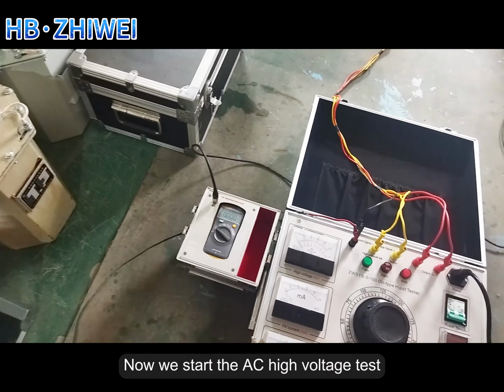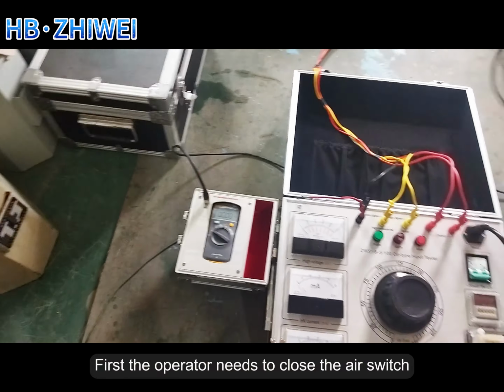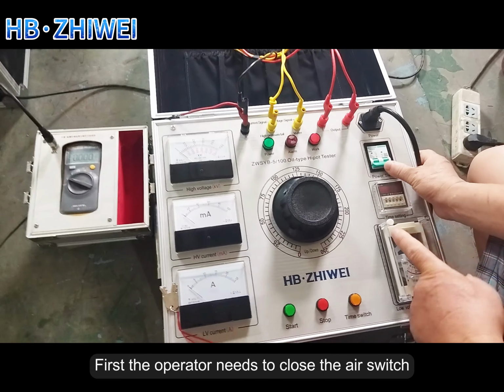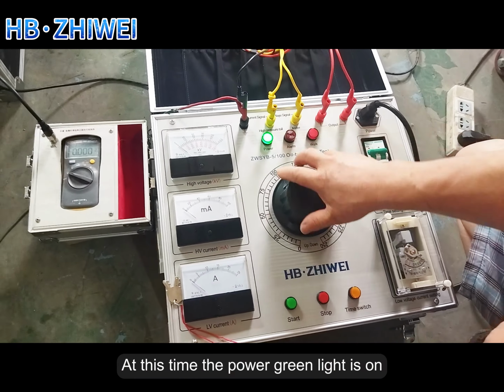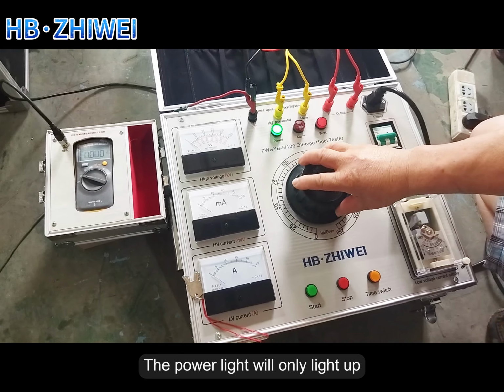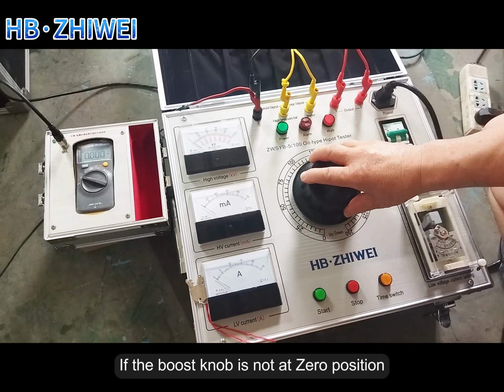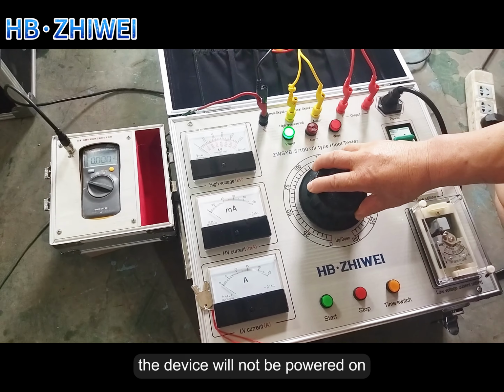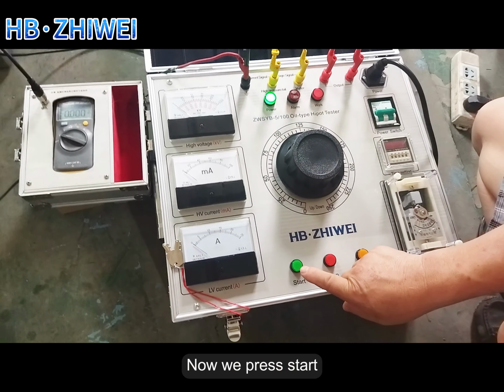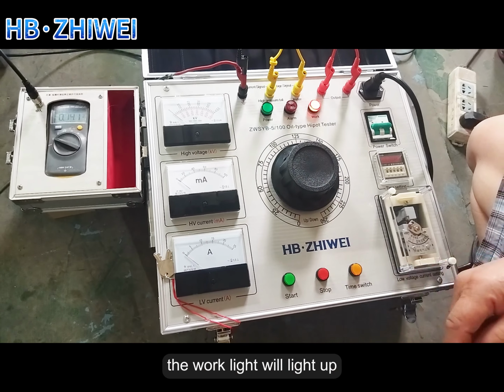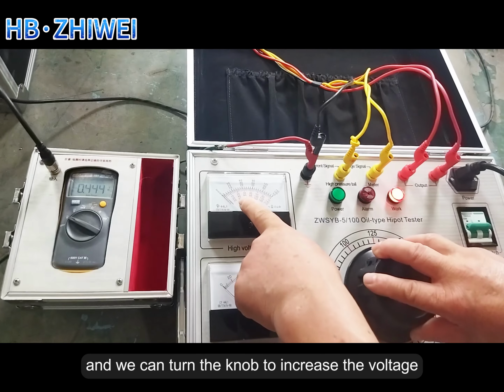Now we start the AC high voltage test. First, the operator needs to close the air switch. At this time, the power green light is on. The power light will only light up when the boost knob is at 0 position. If the boost knob is not at 0 position, the device will not be powered on. Now we press start, the work light will light up, and we can turn the knob to increase the voltage.